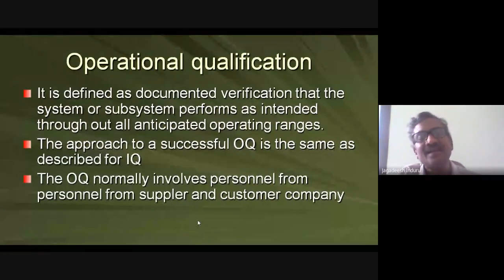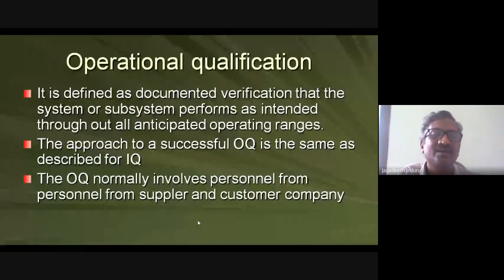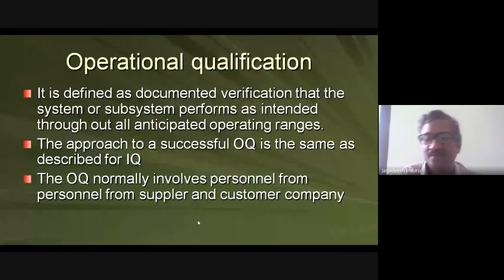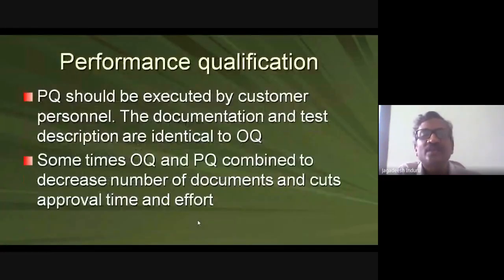OQ work involves both the supplier's personnel and the customer company's factory personnel working together. The factory person learns the methodology and gains confidence with the new equipment. After OQ is complete, you proceed to PQ — Performance Qualification.